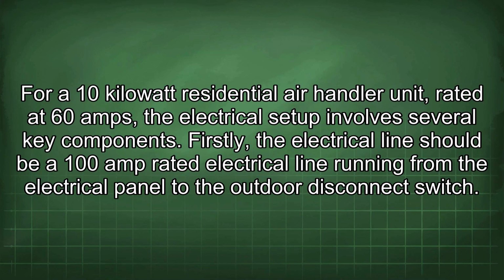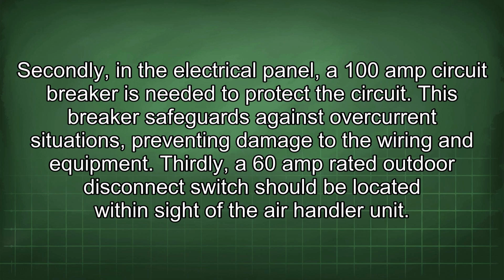For a 10 kilowatt residential air handler unit rated at 60 amps, the electrical setup involves several key components. Firstly, the electrical line should be a 100 amp rated electrical line running from the electrical panel to the outdoor disconnect switch. Secondly, in the electrical panel, a 100 amp circuit breaker is needed to protect the circuit. This breaker safeguards against overcurrent situations, preventing damage to the wiring and equipment.